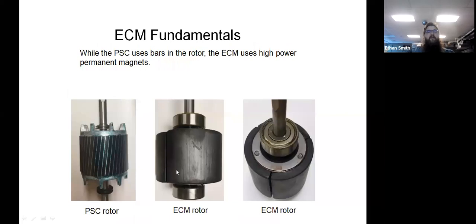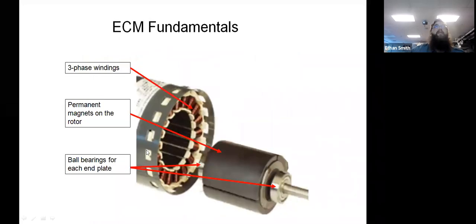Okay. Again, we're going to have typically some type of permanent magnet on the rotor, as opposed to a PSC, which is using that cage rotor. And in the furnace motors, we're typically running ball bearings on both ends, simply because it's easier to lubricate a ball bearing at low speed versus a sleeve bearing.